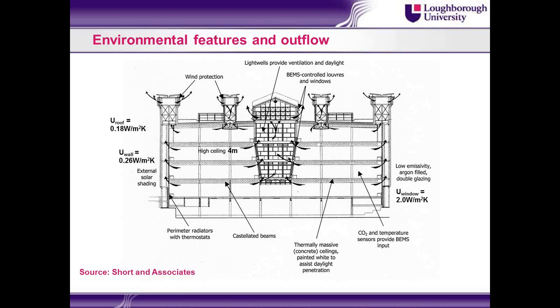So, looking at the outlet paths first, warm air rises and we get a layer of warm air, ideally above head height. So we've got very prodigious floor-to-ceiling heights here of 4 meters, very high ceilings, providing scope for that warm layer to develop below the ceiling. Castellated beams here with holes in them enable that warm air to move across the ceiling and to find its way to the outlet paths. Here is the central light well providing the outlet path in the centre of the building, and then all the way around the outside we've got these dedicated ventilation stacks which are taking the stale air up and out.